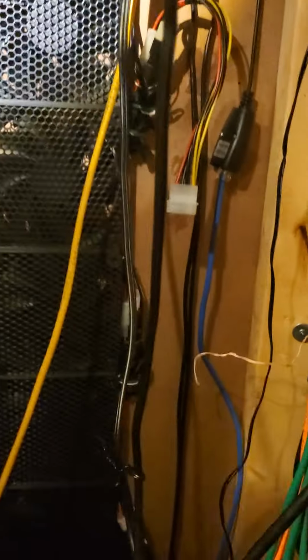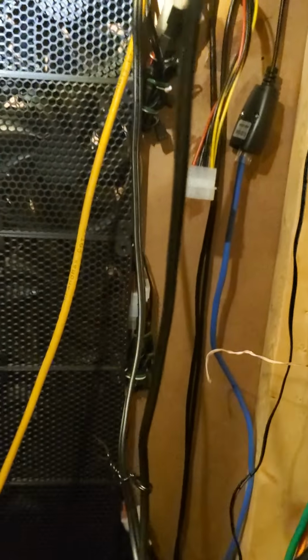This wasn't here before. This was take 2 of the fan arrangement. Take 1 was having them on the door. Take 2 was this, where I tried to make this channel that would go along the side of the rack towards the front, and it failed too. It just would not move enough air, especially given where it is in the rack.